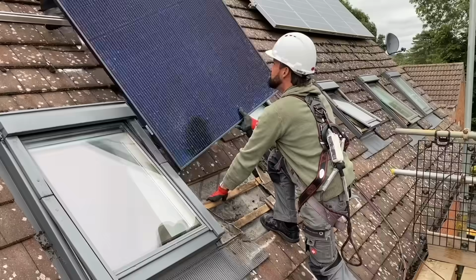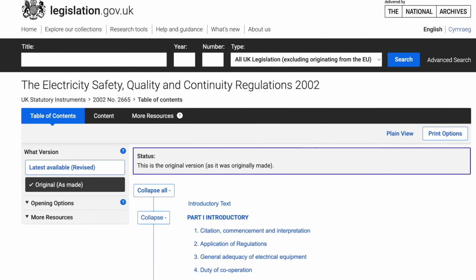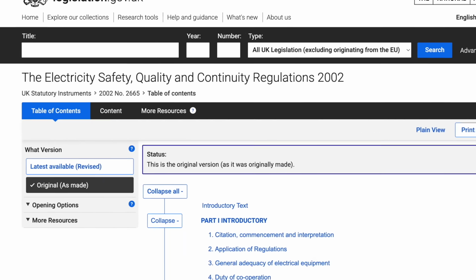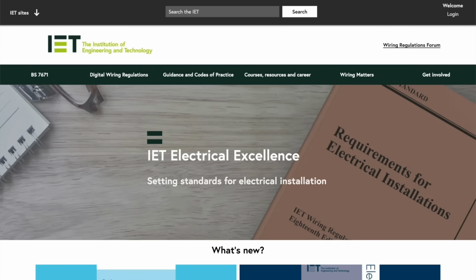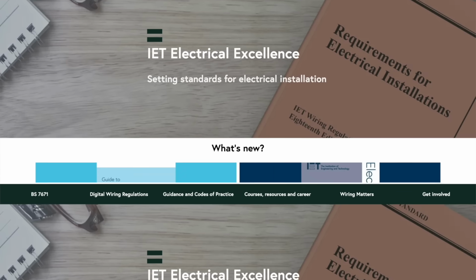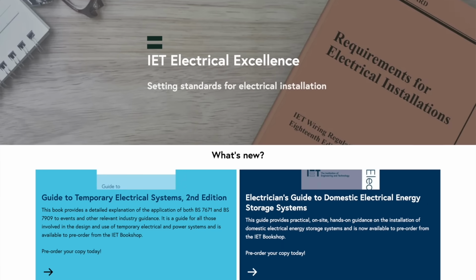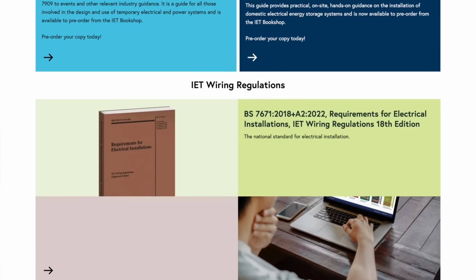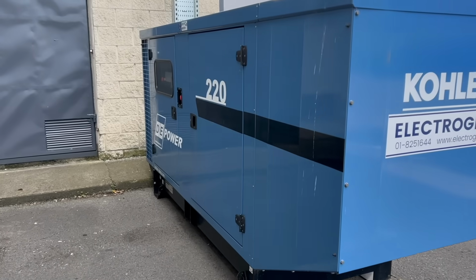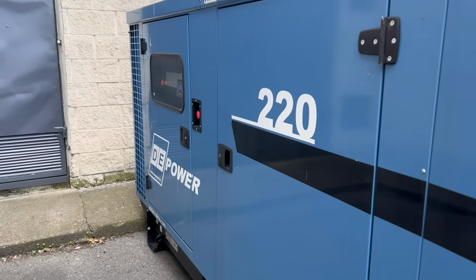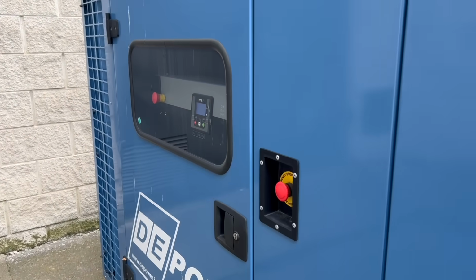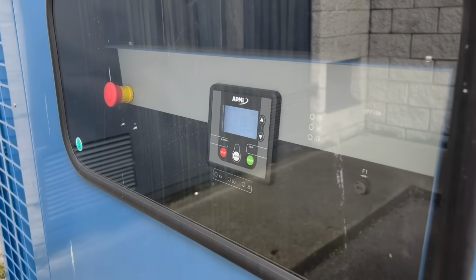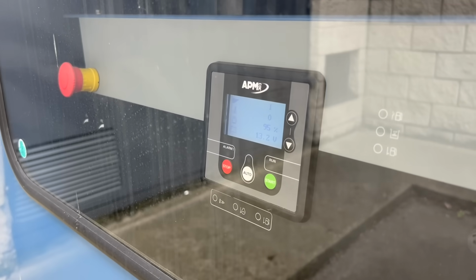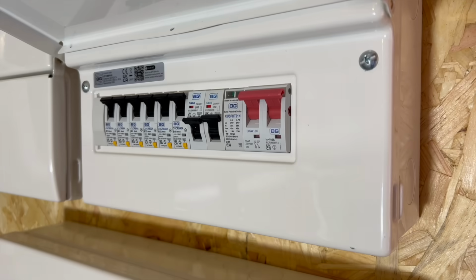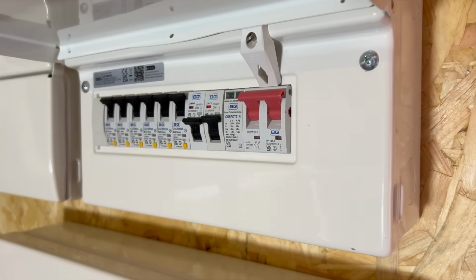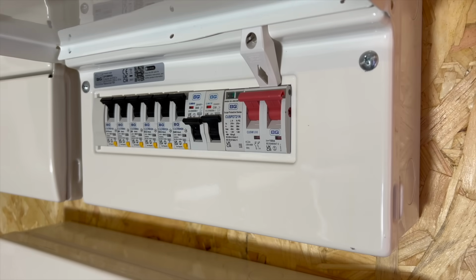The change also requires an amendment to the law, officially the Electricity Safety, Quality and Continuity Regulations, but not everyone is on board. The Institution of Engineering and Technology, authors of the UK Wiring Regulations, has warned that the move could affect older or safety-critical systems such as fire pumps. It also cautions that standby generators and uninterruptible power supplies might interpret the lower voltages as outages, triggering unnecessary switchovers. According to the IET, changes in voltage thresholds could also impact the tripping behaviour of MCBs. This could require updates to the wiring regulations to maintain safety and compliance.